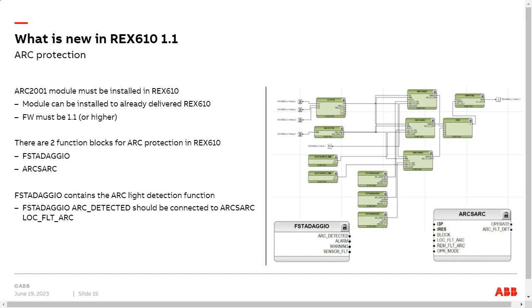If you remember on the previous page, there were two different times for the performance. One was typically 15 milliseconds, and that is if you're only using the arc protection function to trip the device. If you want the quicker one, there's a parameter in the arc function block with which you can directly trigger the output from the function block. It works so that the ARC module is equipped with a microcontroller, and if it recognizes the arc, it directly triggers the output you have configured without going through the application engine of the device. So it speeds up the process a bit. That is the reason there were two different times for light only. You use the arc function to directly trip the output, or if you go through the arc protection function, it goes a little bit slower.